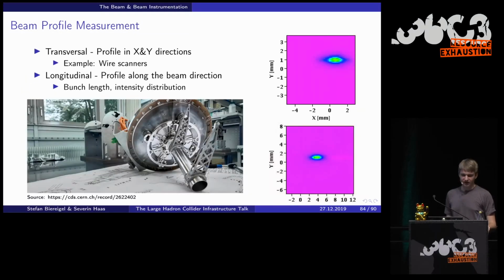All right, then we have beam profile. After the position, which gives you an idea where the beam is, you also want to know its intensity distribution. Basically, when you would do a cut through the beam pipe somewhere, you want to know what the intensity profile looks like. For that, we have basically 2 measurement systems. One measures the profile in X and Y directions. So if you really would do a cut, it gives you something like this. It's, for example, done with wire scanners, which is a literal, very thin wire that is moved through the beam. Then the current that the beam moving through this wire generates is used to generate such a profile map when scanning with this wire.